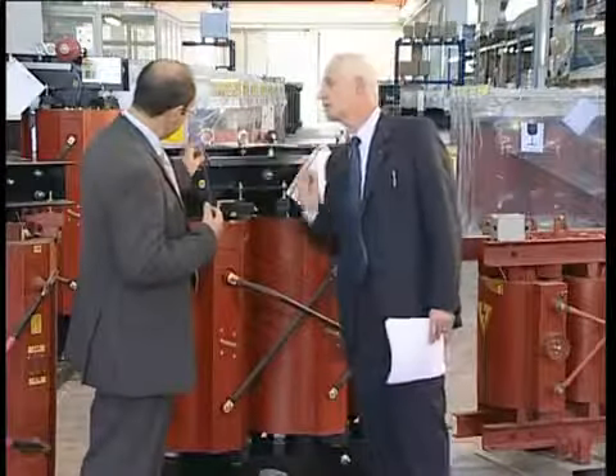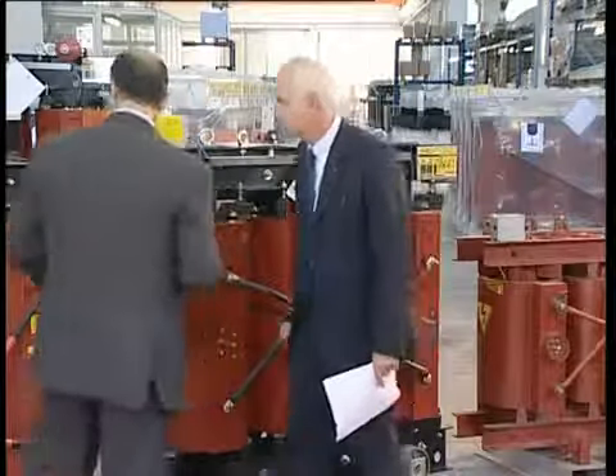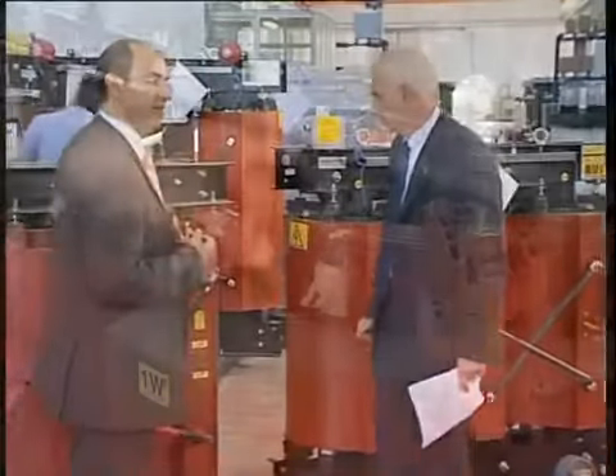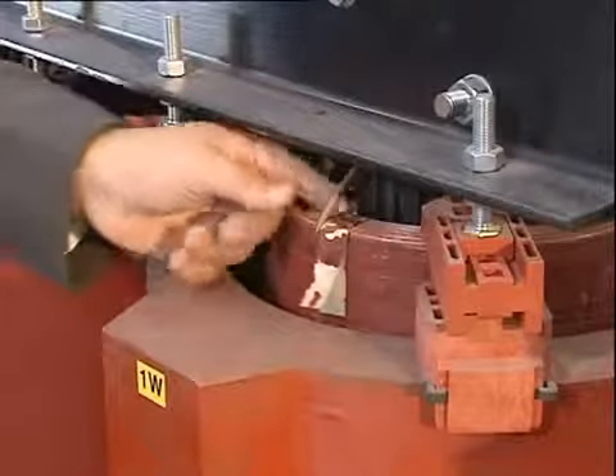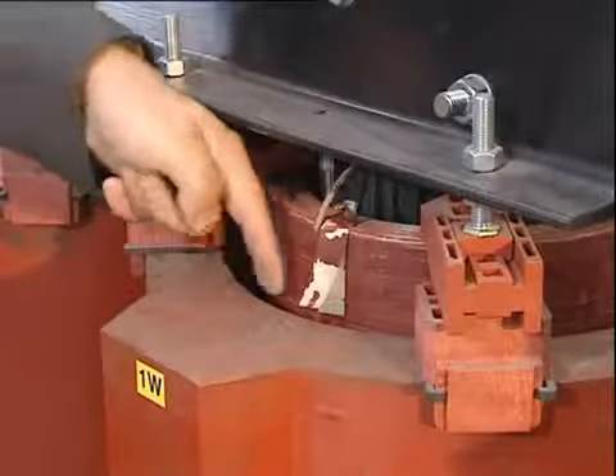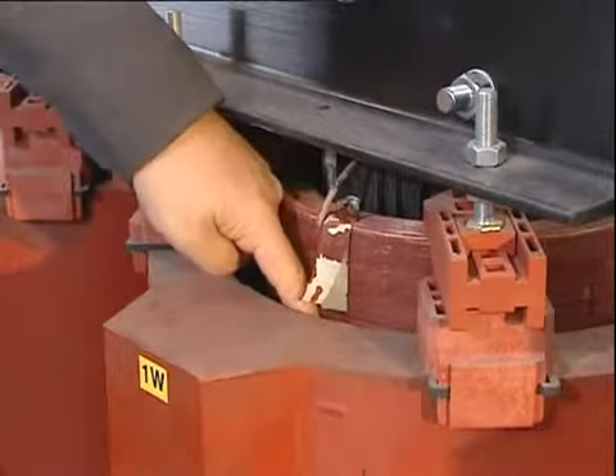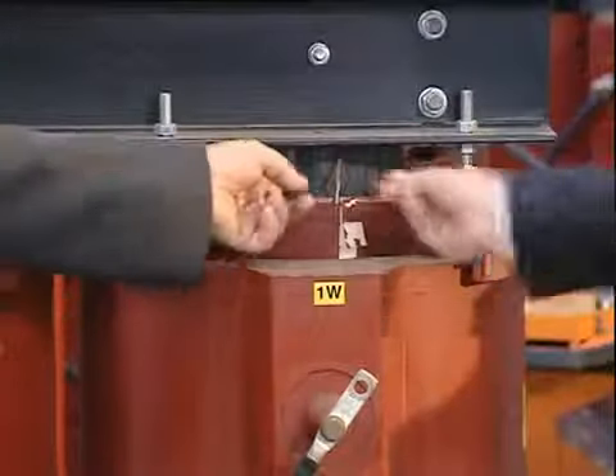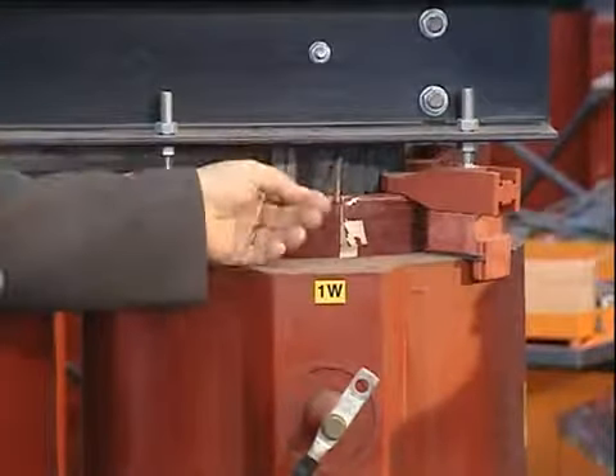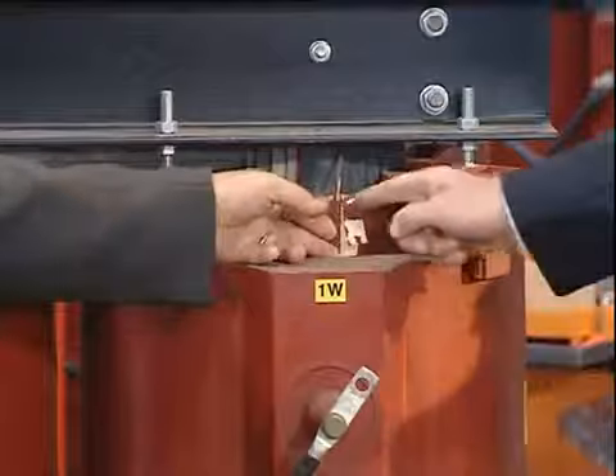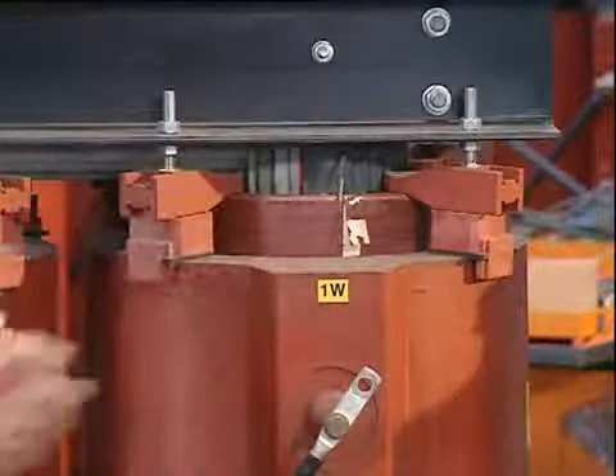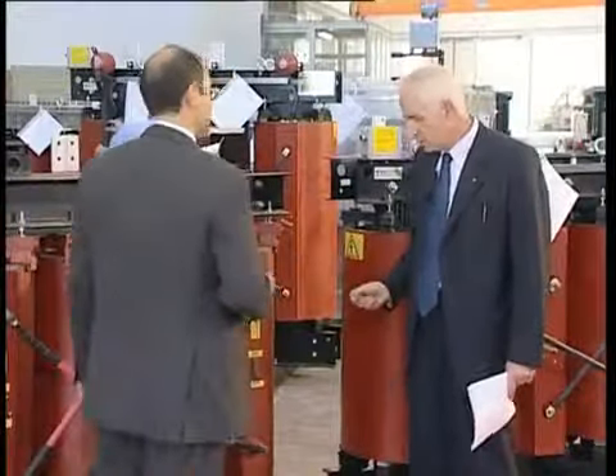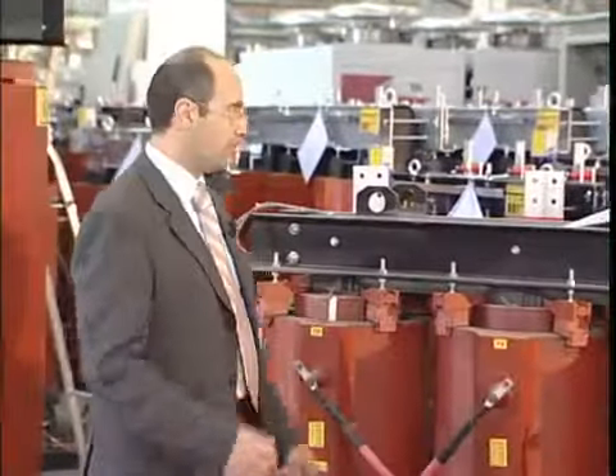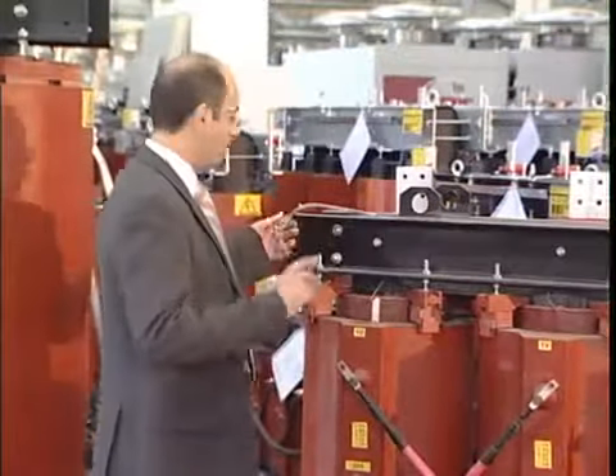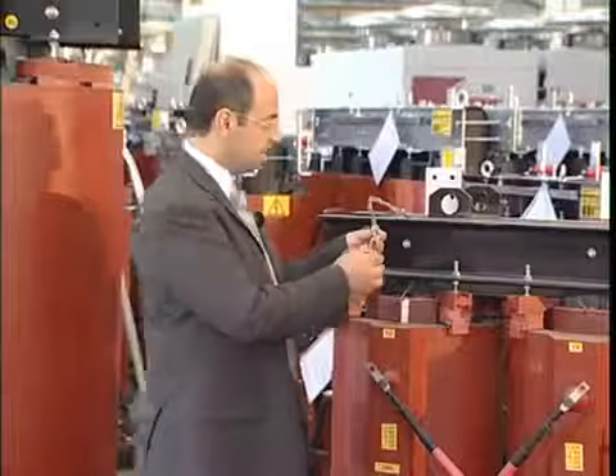What about the other transformer? In this transformer instead, we notice that there is no central ventilation duct in the secondary winding. A ventilation duct between the core and the winding. What about this probe? This probe is not extractable, but integrated in the winding. Therefore, in case of failure, it cannot be replaced. There's no hope. Do these items fail often? Sure, these probes can certainly break down. I would like to draw our public's attention to one detail.